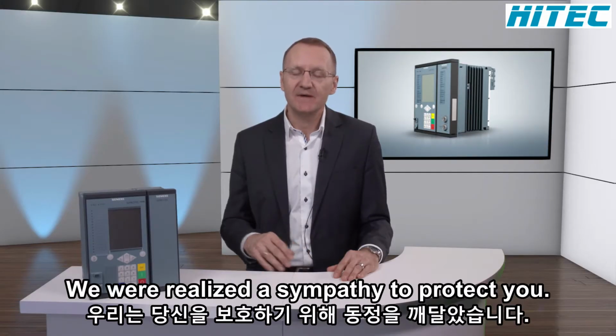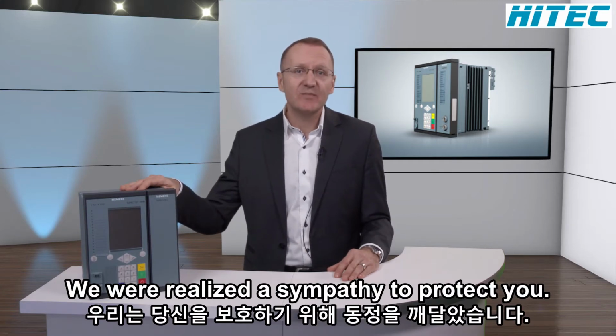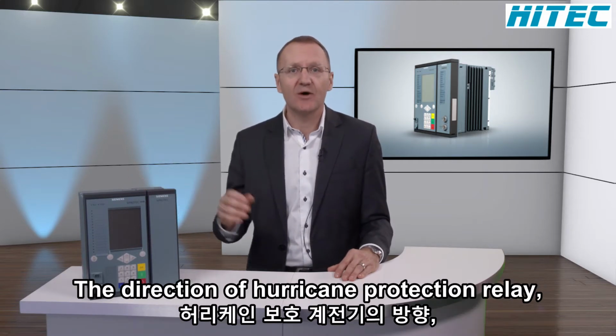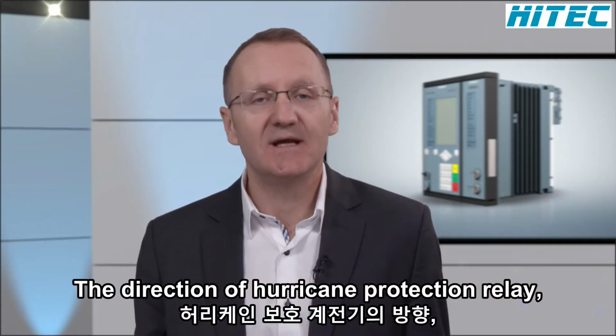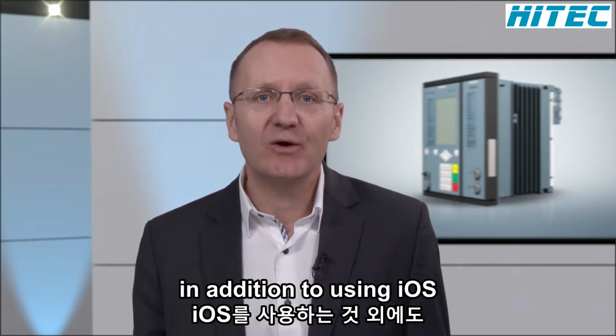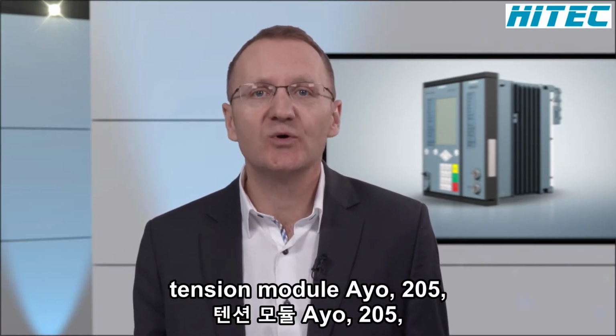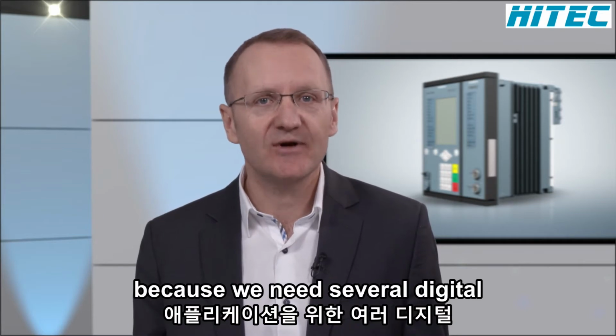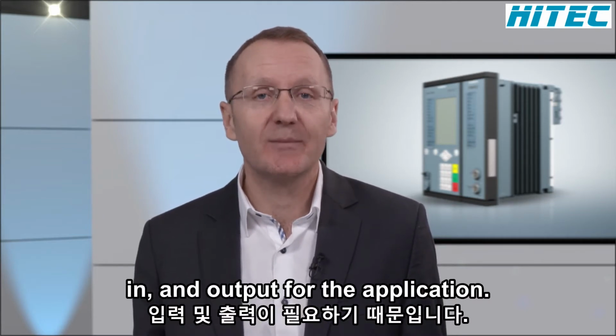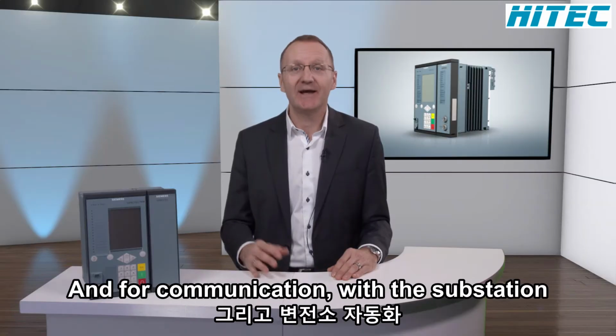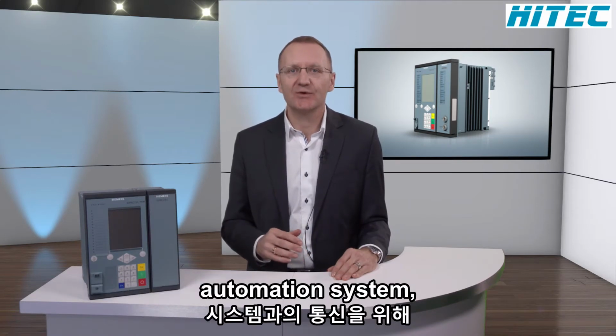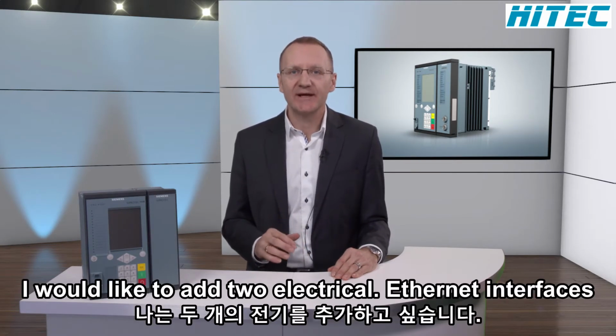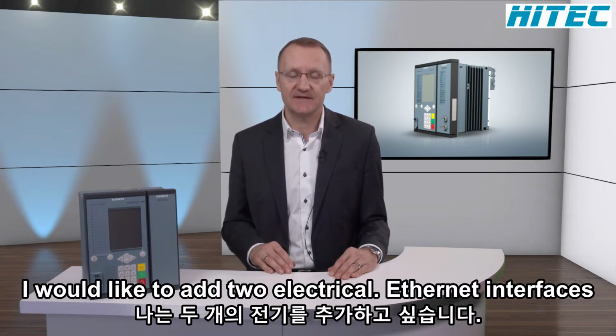As an example, we will realize a simple feeder protection with a directional overcurrent protection relay. In addition, we use an I/O expansion module, IO205, because we need several digital inputs and outputs for the application. And for communication with the substation automation system, I would like to add two electrical Ethernet interfaces.